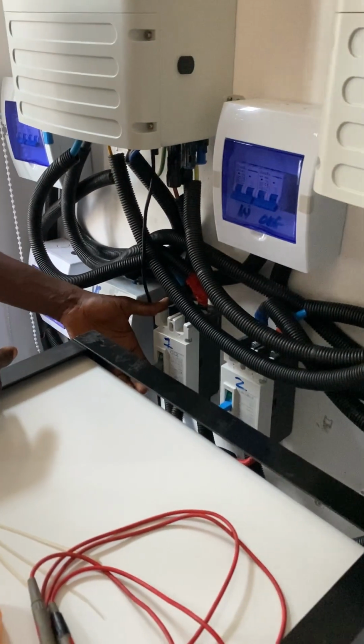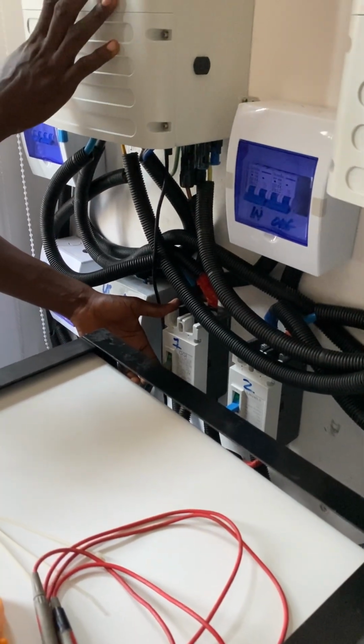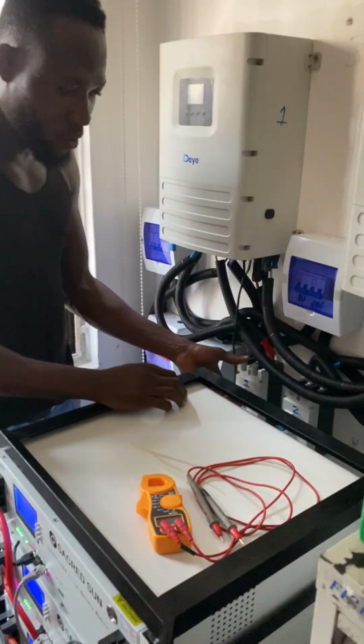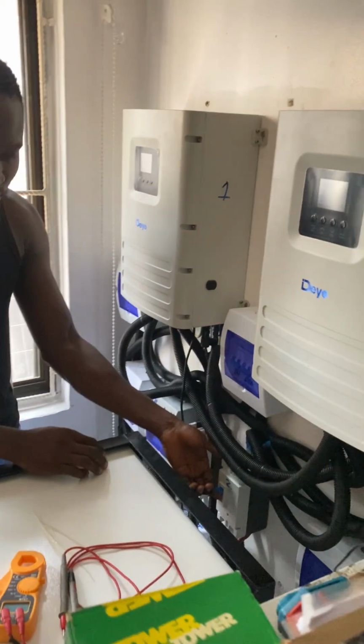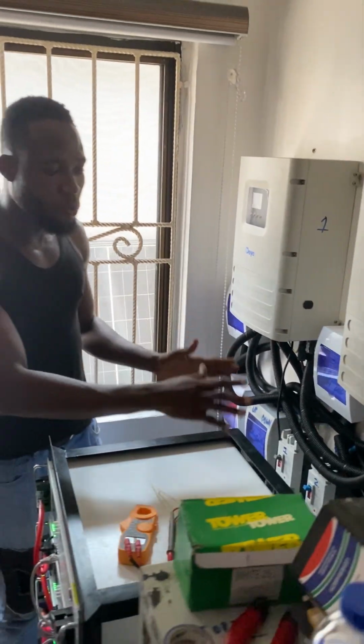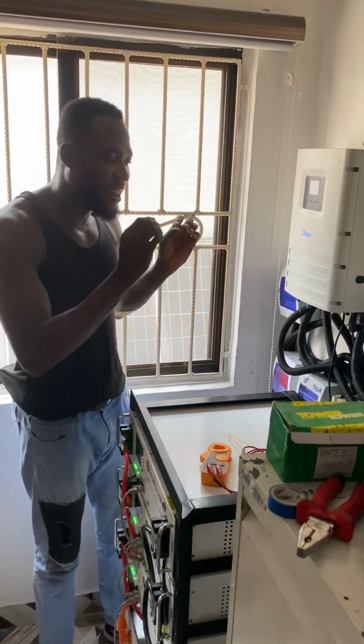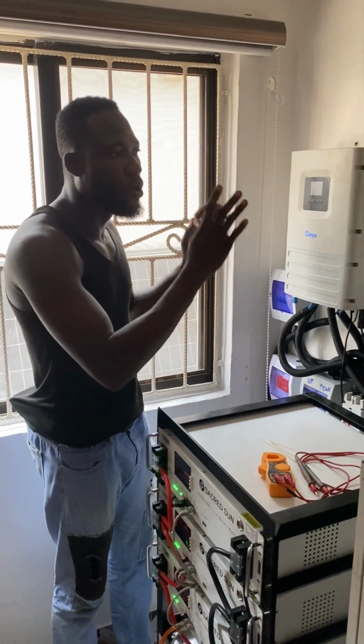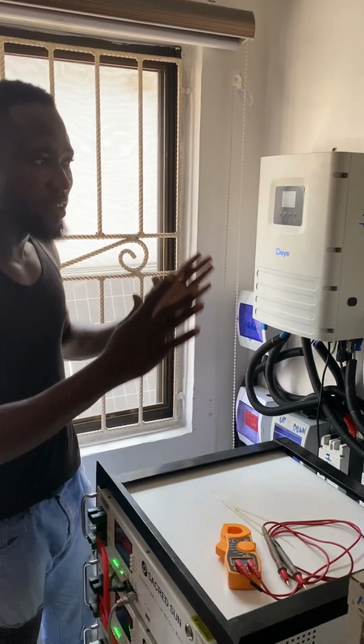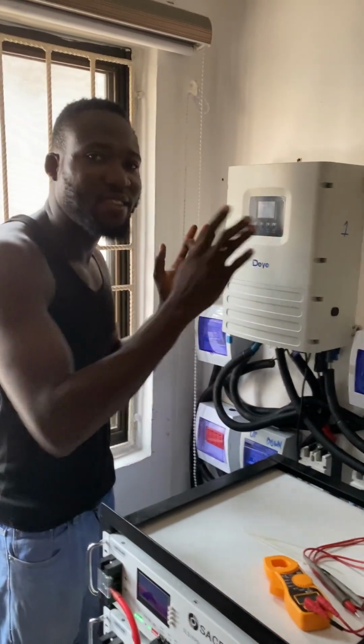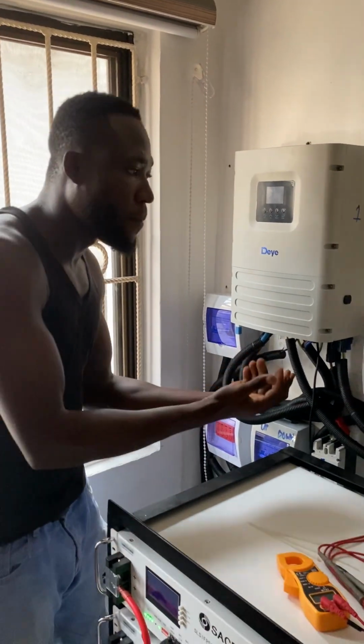So you power it on for the master inverter. These are the master inverters - you power on inverter 1, you power on inverter 2. Immediately after you power your battery on, the next thing you need to do is turn on your inverter. As you know, these are 6 kVA Deye hybrid inverters. You need to power it at the bottom.